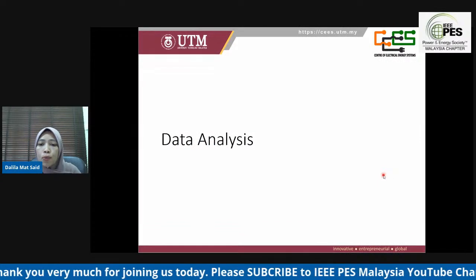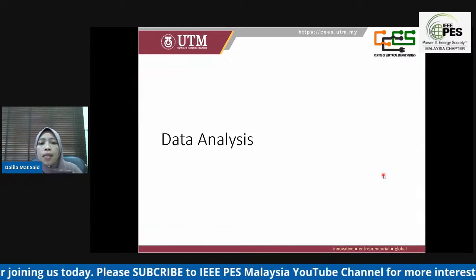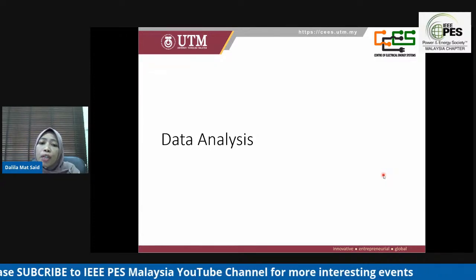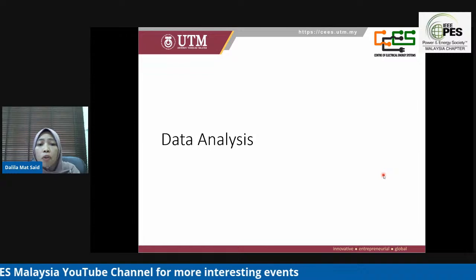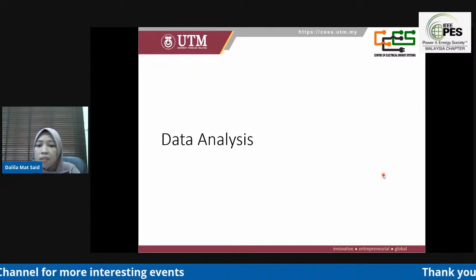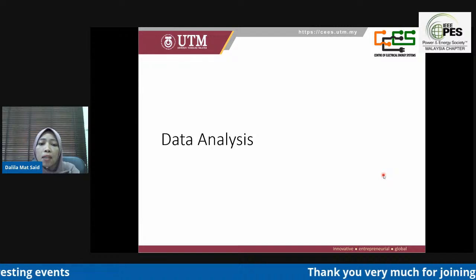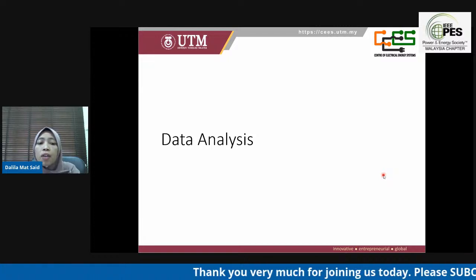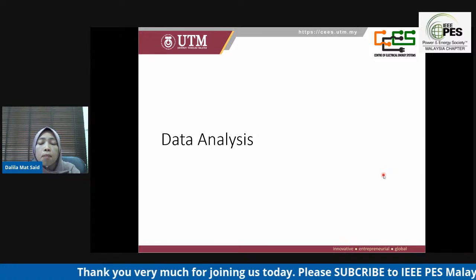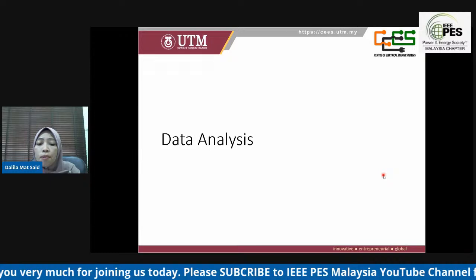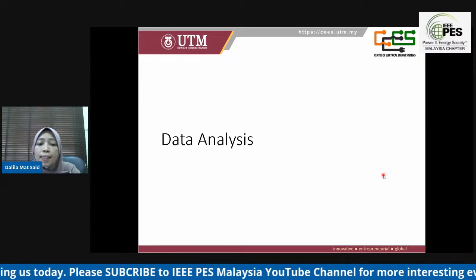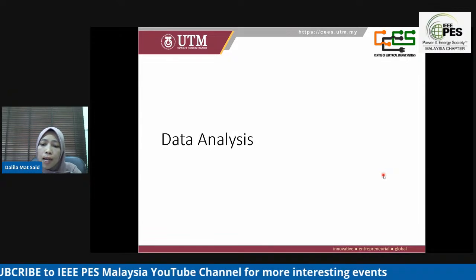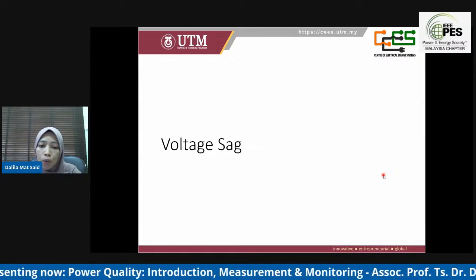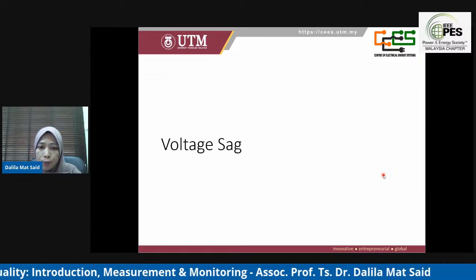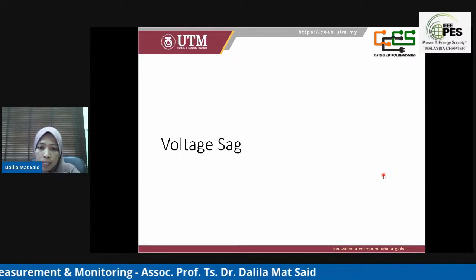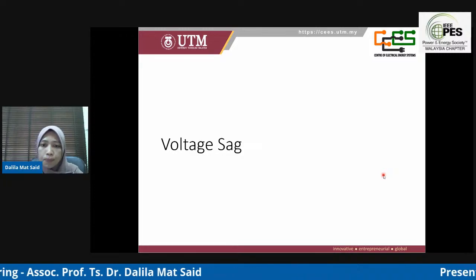So next, we want to go to data analysis. Analysis may be an engineer evaluating meter data, or even performing computer simulation, or today maybe artificial intelligence software looking at waveforms and making a determination. Every problem can be solved with the right clues, but sometimes clues lead you down the wrong path. Therefore, proper analysis needs to be performed. So I start with an example of data analysis for voltage sags. In this section, I will cover voltage sags, harmonics, and also other PQ problems.